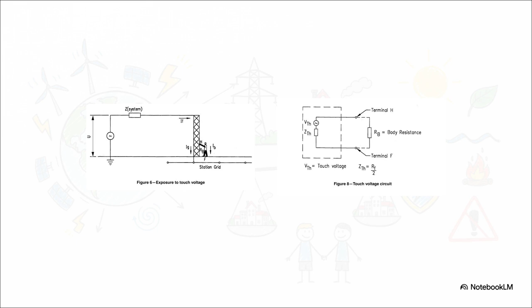The safety of the grid literally relies on treating a person as a biological resistor, labeled as R_B, in a massive electrical loop. By assigning an accepted average resistance value for the human body, usually right around 1,000 ohms depending on the specific standard, engineers calculate the exact body current that will flow through the person during a fault. This ensures the physical ground grid is designed to keep that current well below lethal thresholds.